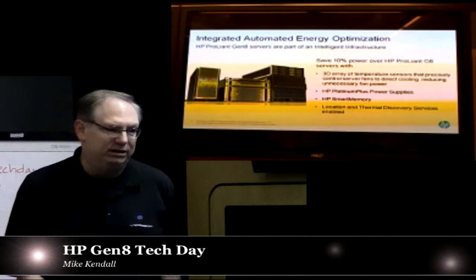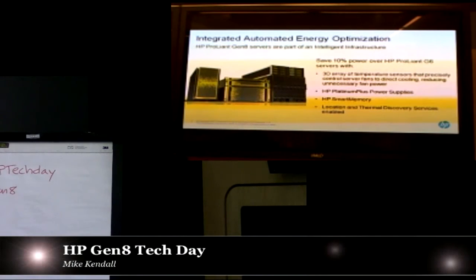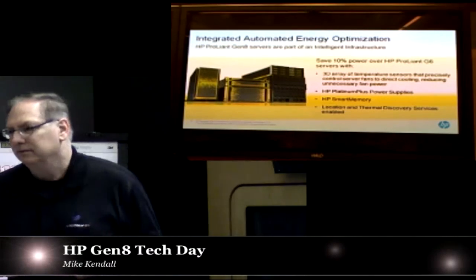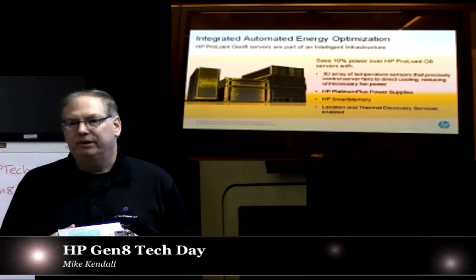The next thing are Platinum Plus power supplies. Let me walk over here for a second. Are you guys familiar with the 80 Plus certification group? For those that may not be, there's a power supply certification group called 80 Plus, and they actually lay down the rules of what power supplies' conversion efficiencies are, as well as total harmonic distortion, power factor correction - things that can impact the efficiency and the amount of power you can actually extract from a given circuit.